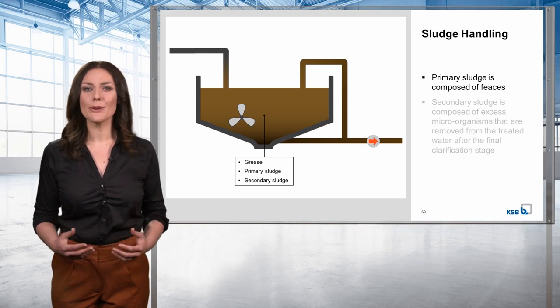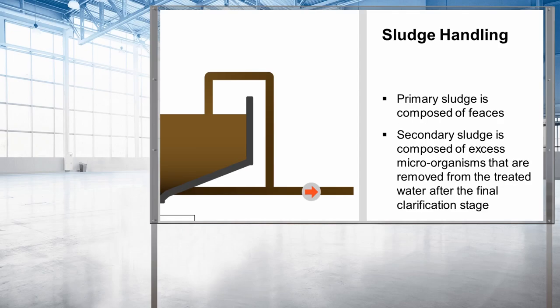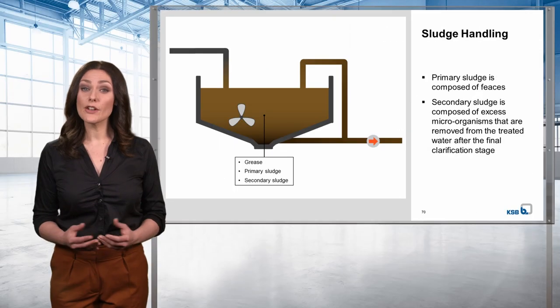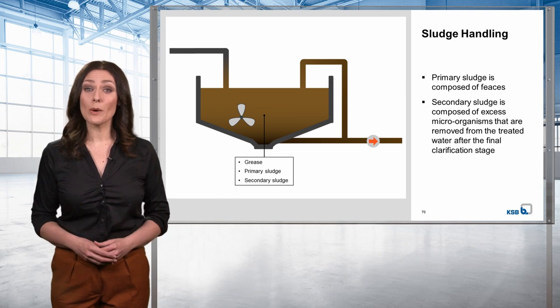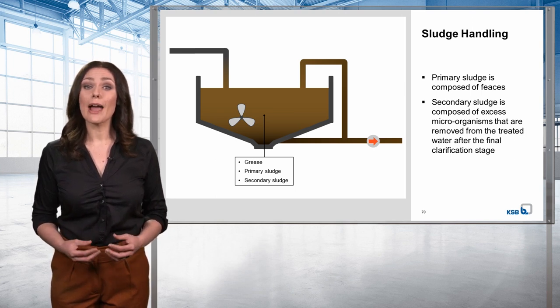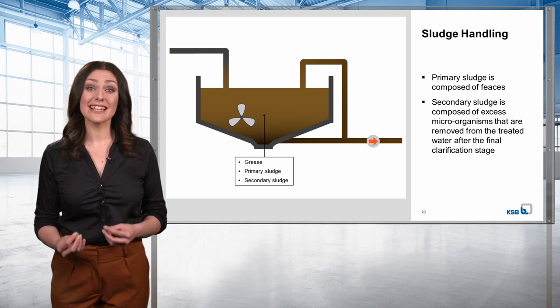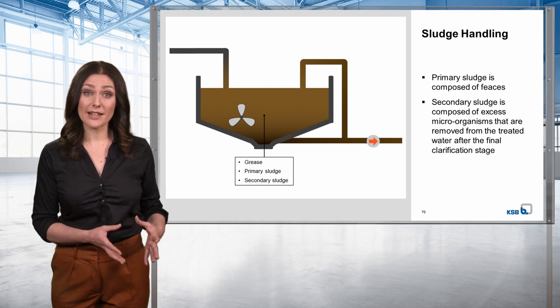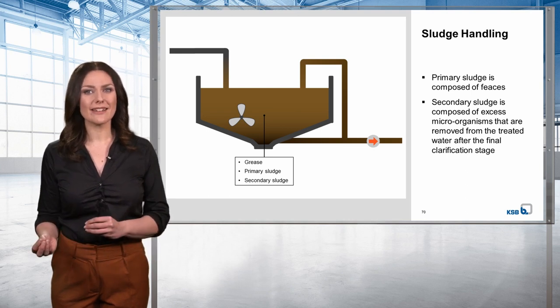Primary sludge is mainly composed of feces. The terms secondary or excess sludge define excess microorganisms that are removed from the treated water after the final clarification stage. The different types of sludge can either be treated together or separately. The first option is mainly used in smaller wastewater treatment plants, where primary and secondary sludge are treated together in so-called mixed sludge tanks — for example, 60% primary sludge and 40% secondary sludge.